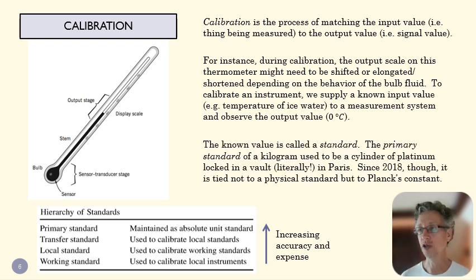And so that means that's something that we need to do in calibration. And in order to do that, we're going to use what's called a standard. A standard is a measurement, is some physical quantity that we know what the quantity is, right? So think about the kilogram. What is a kilogram? Well, at one point, in fact, not that long ago, a kilogram was a cylinder of platinum that is locked in a vault in Paris. That was the kilogram. And every other standard we compared to that kilogram to make sure that it was actually what a kilogram was. Now you can see the problems with that. And one of them is that everything changes. You know, the more we know about quantum, nothing's stable. And so even that platinum would change its mass over time.